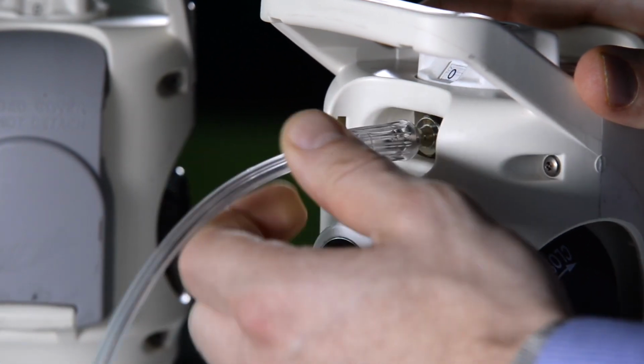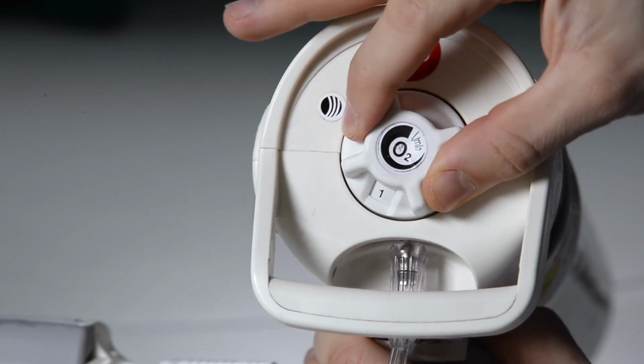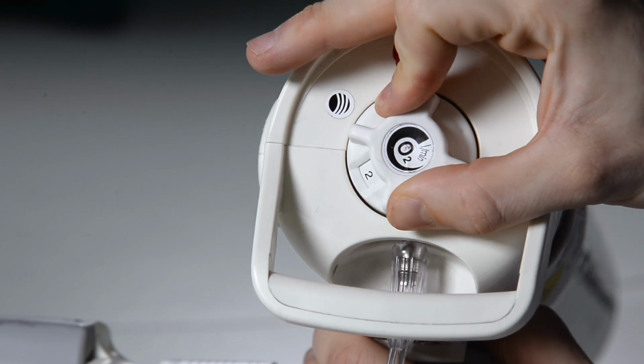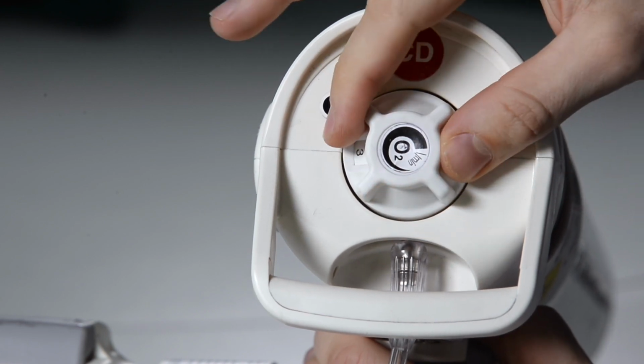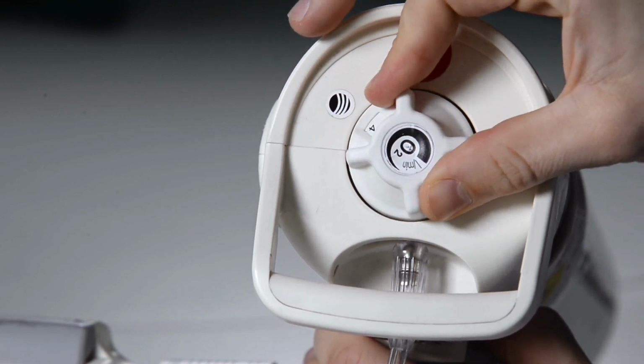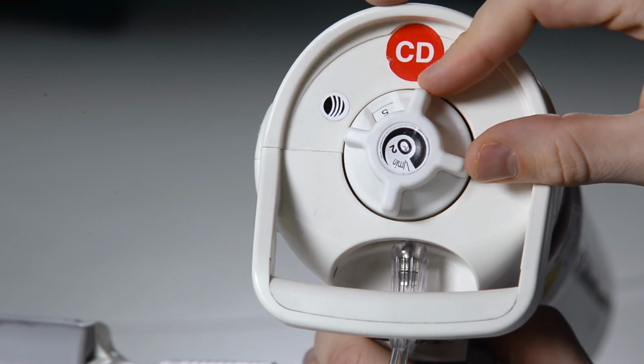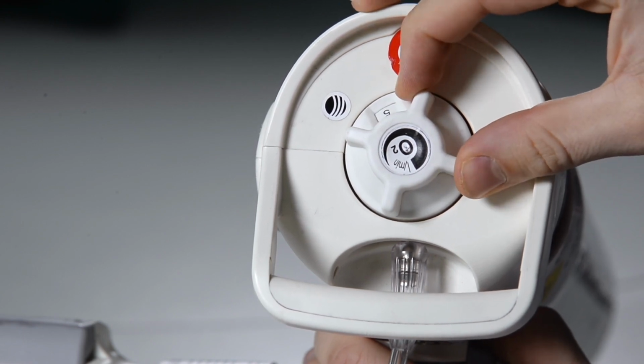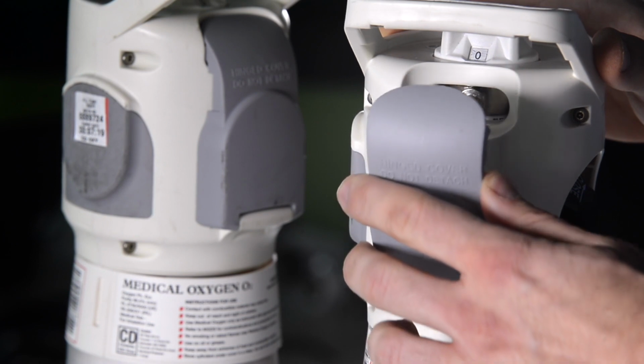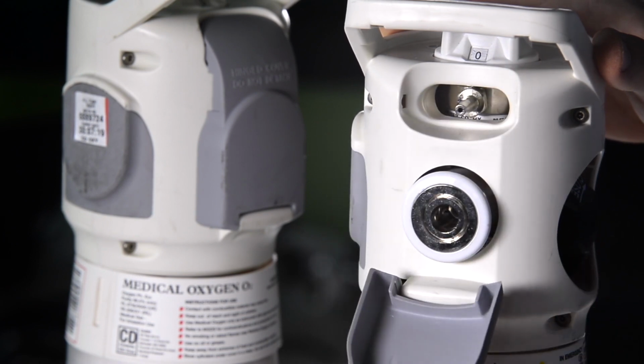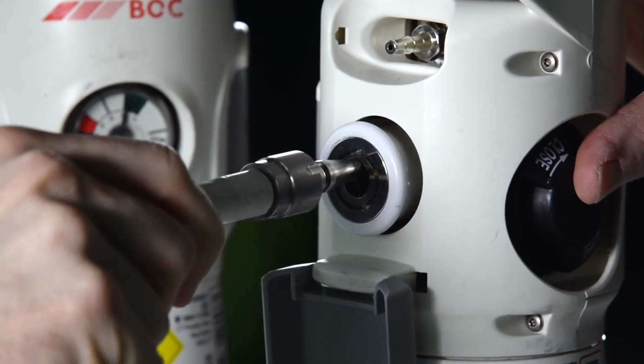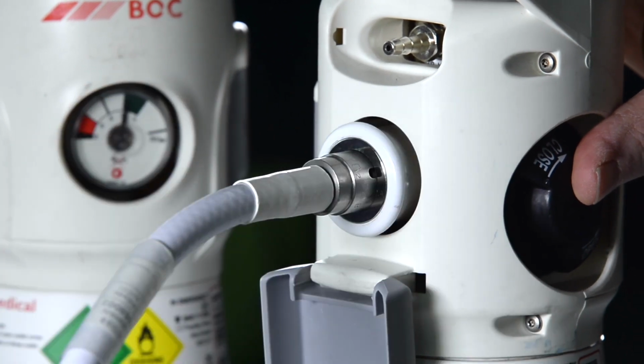One is fitted with a fir tree type connector where you can fit a standard 6mm tubing. This connector is supplied from a variable flow selector giving flow rates up to 15 litres per minute. The other outlet is a UK standard Schrader connector that accepts a product-specific probe to obtain a 4-bar gas supply for feeding medical equipment.